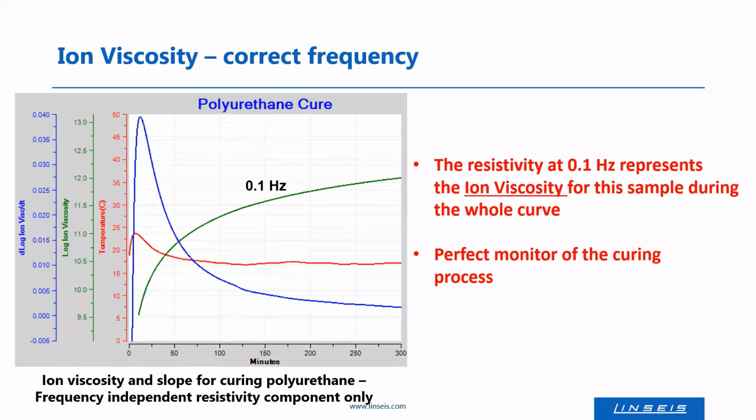So to summarize, it's important that you realize that for dielectrical analysis, you need the ion viscosity to monitor the curing process. The ion viscosity is the frequency independent part of the resistivity, and the ion viscosity needs to be filtered for correct frequencies. When you are doing measurements, try to do multi-frequency measurements and filter out the correct ones.